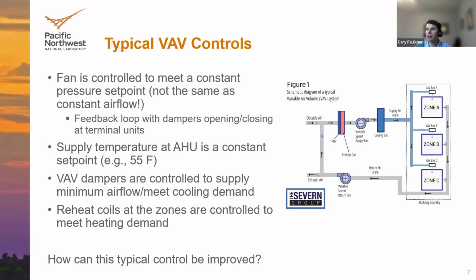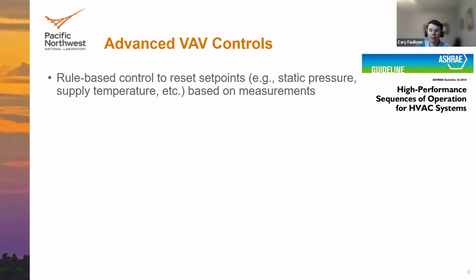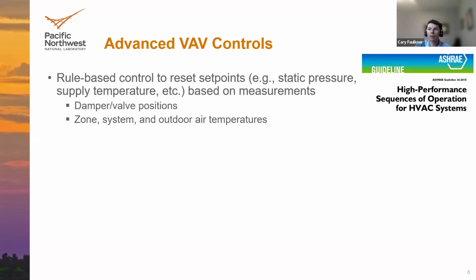But maybe we can think about how these controls can be improved, which is going to inform some modeling research later on. So there are more advanced VAV controls, generally separated into a few different categories. The first one being rule-based controls. These rule-based controls can reset set points like static pressure or supply air temperature based on measurements taken from the building system. One example of this is Guideline 36, which measures things like the damper and valve positions or temperatures for the zone, air handling system, and outdoor air temperatures, and uses that to reset those set points strategically, in some rule-based manner that's more intuitive and interpretable, but requires implementing some sort of logic to do the control reset based on these measurements.